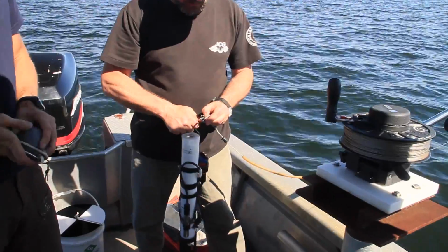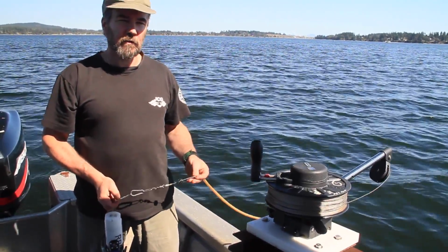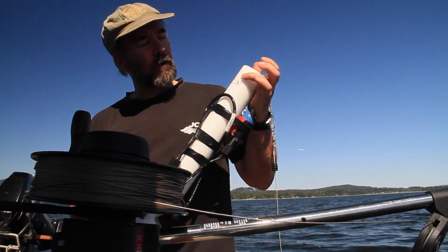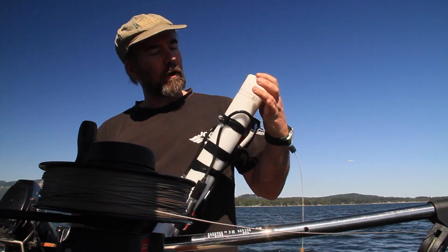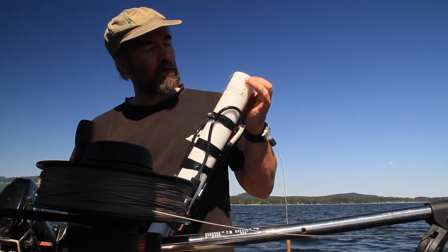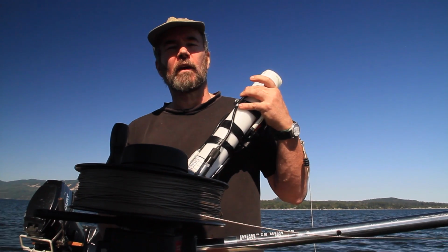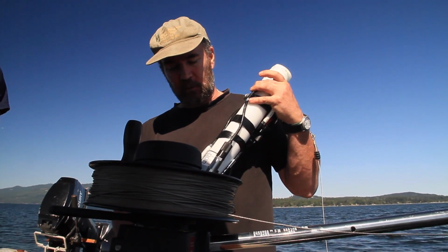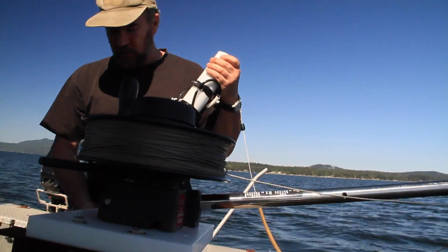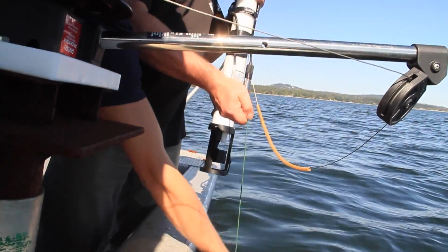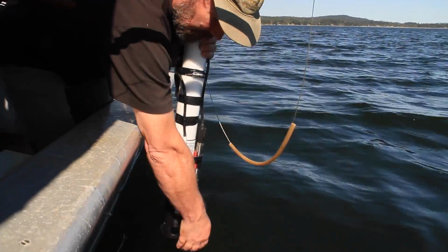This gets clipped onto the top of the CTD, and you always clip it on inboard. Okay, nothing goes over the side of the boat until you're sure it's secure. Okay, so there's an arrow on the end cap. There is an off and an on position on the body. To turn on, turn clockwise to on, and the body will shake. There's a little shaker in it so you can feel it buzz, and that will tell you it comes on. Once we've got this on, then we'll put the weight in the water, and the idea is you make sure everything's really safe. So you don't want anything to jerk over the side nastily. So you take the weight on there.